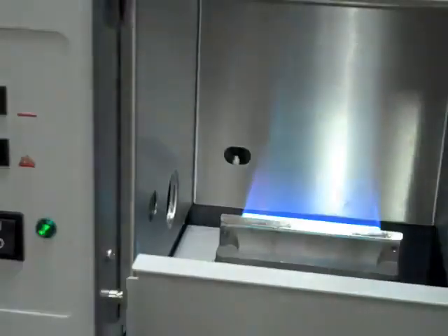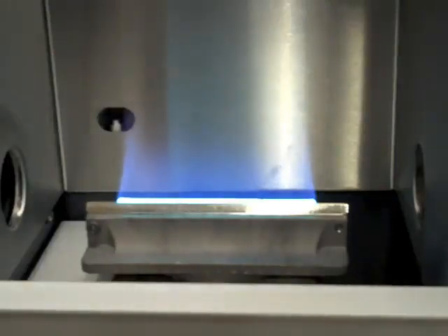Turn on the burner with the black button on the left-hand side of the instrument. The flame should burn with a bright ribbon of color along the edge of the slot. This ribbon should have a uniform straight edge to it. If there are any breaks in the ribbon, ask the instructor for help in cleaning the burner head.